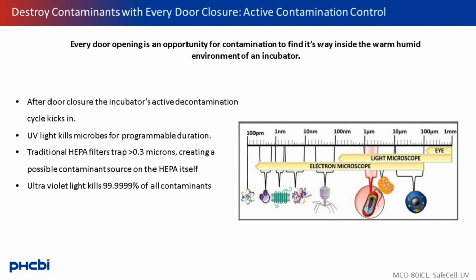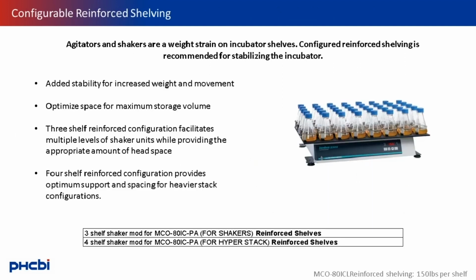Unlike the traditional HEPA filter, UV light destroys 99.999% of all contaminants, instead of trapping them inside the incubator space. Heavier configurations, usually orbitals and shakers, can create a strain on the incubator shelves. This can be overcome by configuring reinforced shelving for added stability. We have two types of configurations in place that are best suited for different applications. The 3 reinforced shelf option available was configured with cell shakers and orbitals in mind due to the weight and space demands of this application.